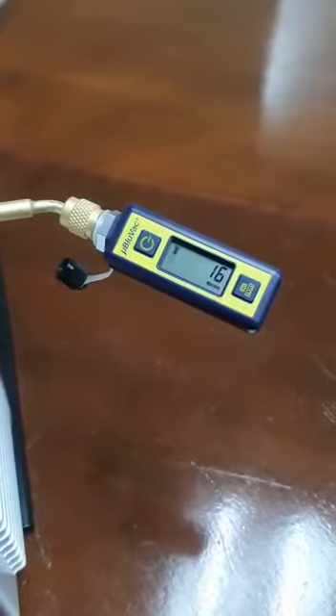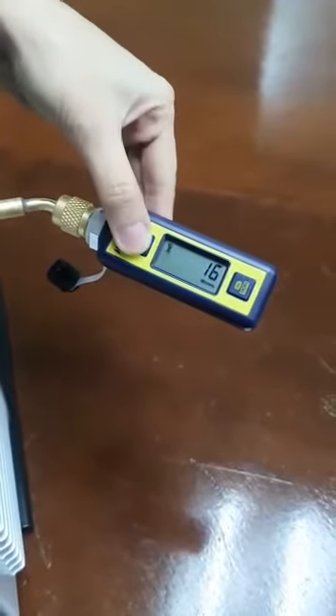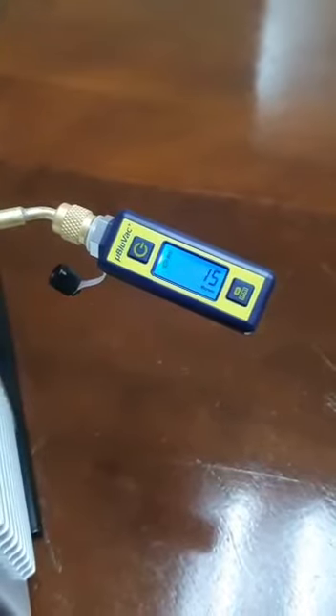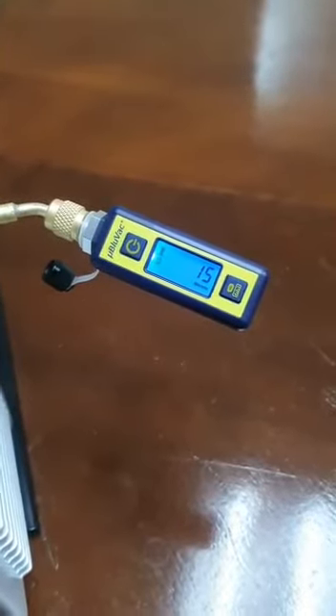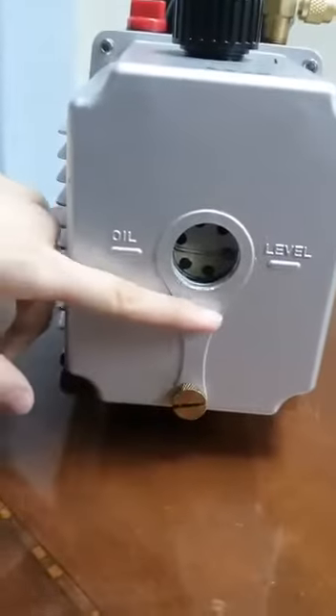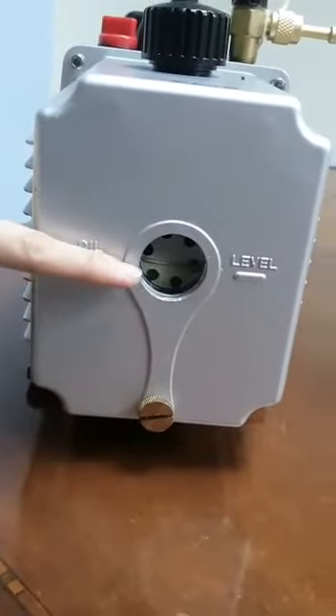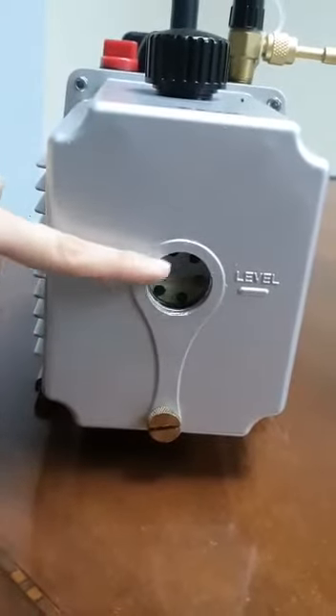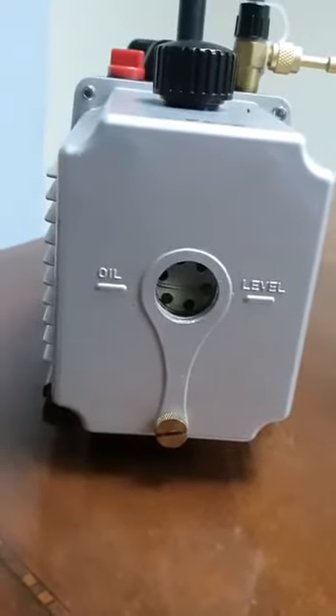After a few seconds, you can see from the gauge that our vacuum pump is already reading in the low micron range and it keeps on dropping. At the same time, you can see the vacuum pump oil reference level is at an adequate amount and in crystal clear solution, meaning there is no contamination happening yet.